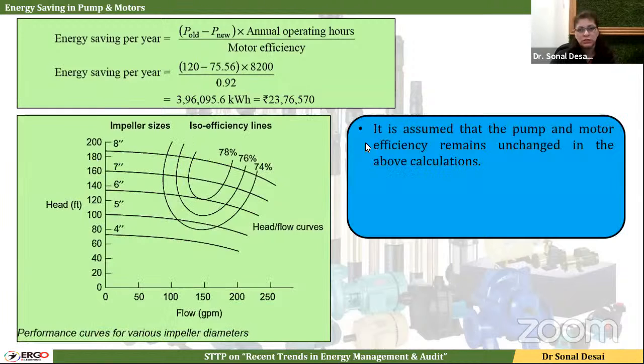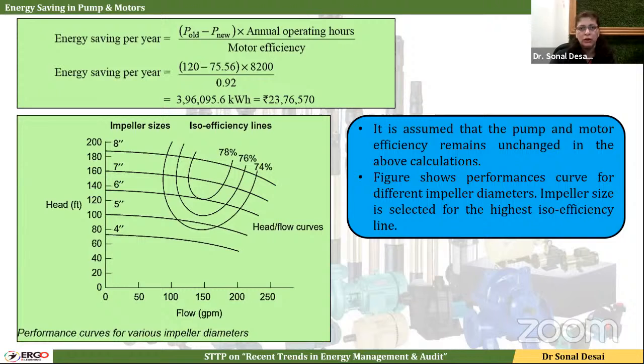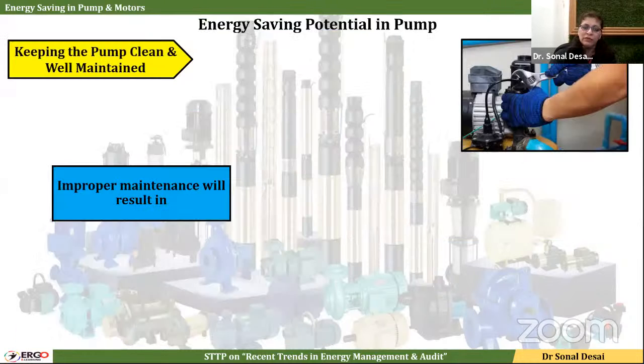So it's a huge amount. Hence, that impeller cost is just nothing. Over here, it is assumed that pump and motor efficiency remains unchanged when we trim the impeller. Ideally speaking, they will also change. And the performance curve followed over here is this. Some more energy saving potential: always keep the pump in clean condition and maintain it routinely.